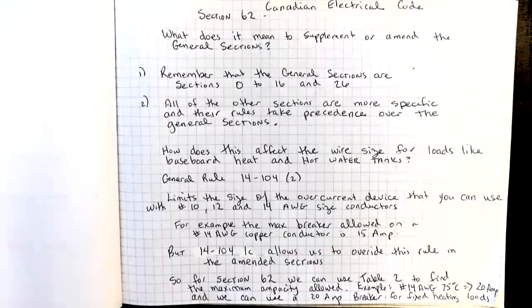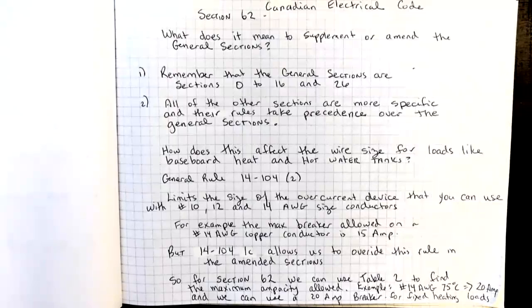But if you look at 14-104(1)(c), it allows us to override 14-104(2) in the amended sections. So for section 62, we can use Table 2 to find the maximum capacity allowed, which is 20 amps, and then we can use a 20-amp breaker for fixed heating loads.